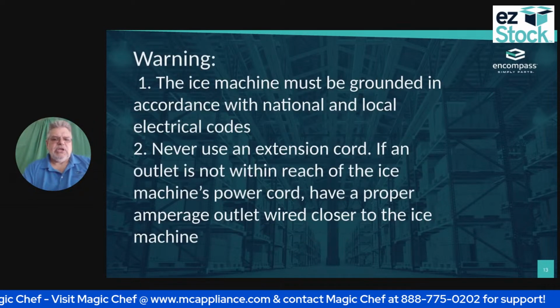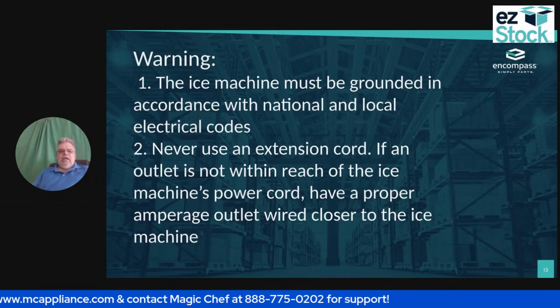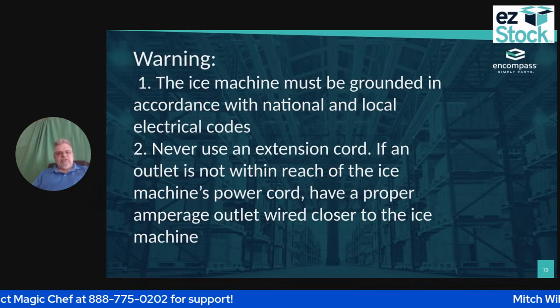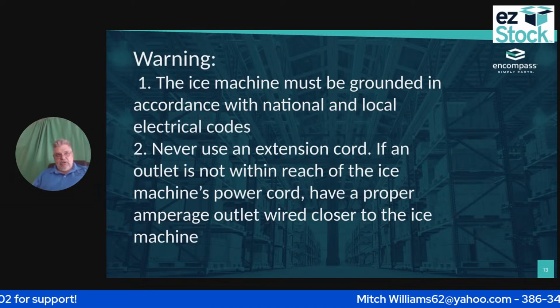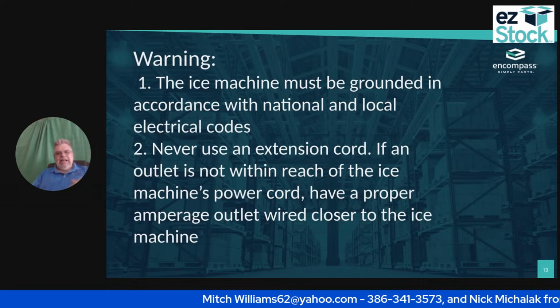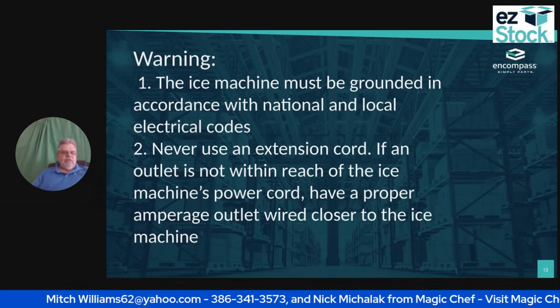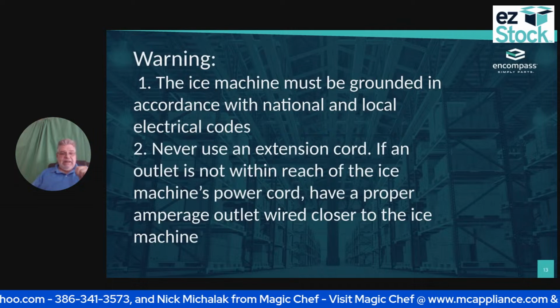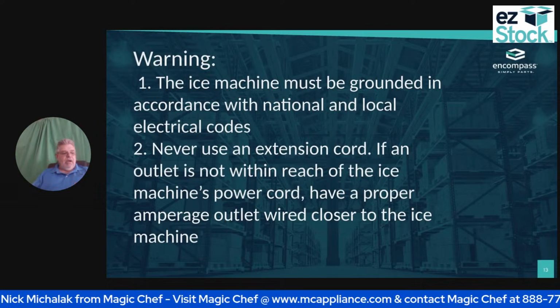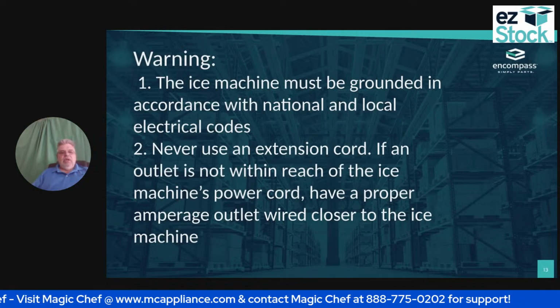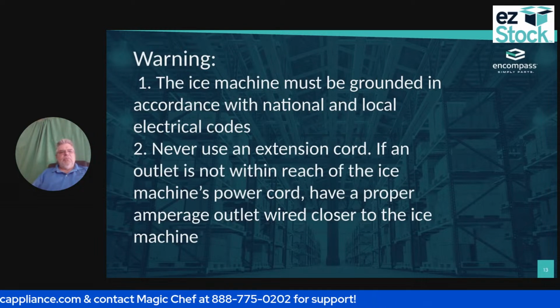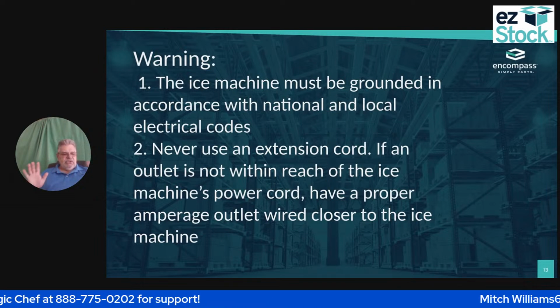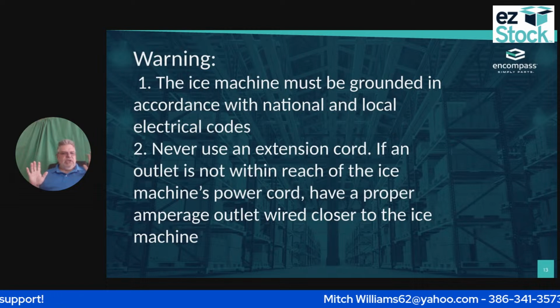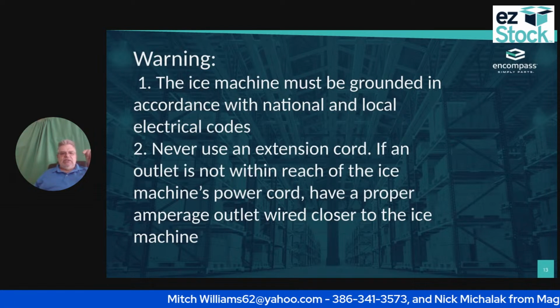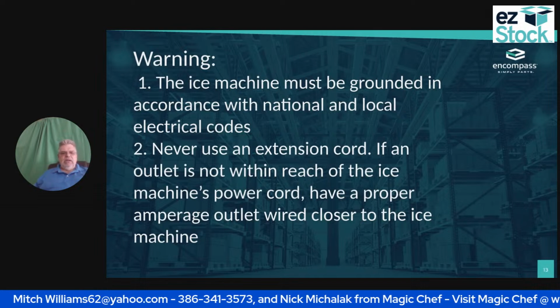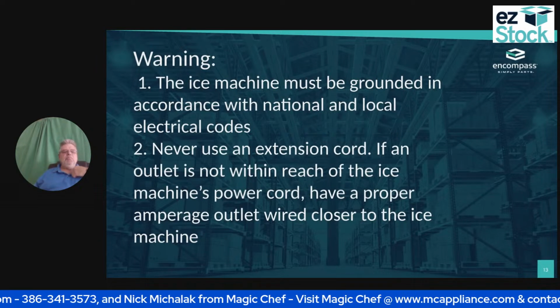The ice machine must be grounded in accordance with national and local codes. Like I said, this is a 110-volt ice machine. You can't cut off that ground plug. It's safety. If the inspector comes in and finds out that you have cut it, then you as a technician are in trouble. If you come out and find a unit that somebody else has cut, you have to stop, get the customer, and walk away from it. Say, ma'am, I'm sorry, I can't work on this, because as soon as you do something to this unit, I've put my name on it, and I'm responsible.